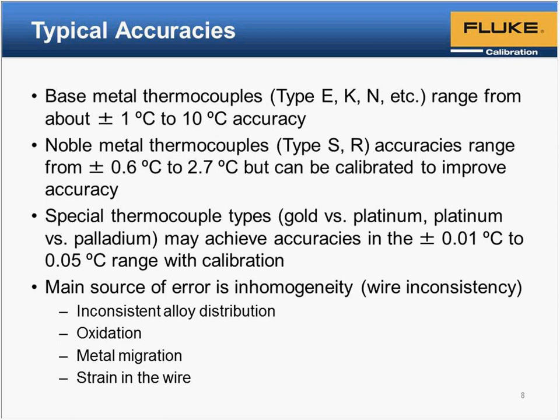So the sources of error, again, are the items that we list here, and some of them change a lot over time depending on how the thermocouple is used. Inconsistent alloy distribution has to do with when the thermocouple is made: how well does the manufacturer mix the alloys together and keep them consistent throughout the length of wire? Oxidation over time, especially at certain temperatures. Then there is metal migration, where a section of wire is heated to a point where the metal vaporizes, and the metal vapor moves and then recollects at a cooler spot in the thermocouple. So you start building up a quantity of a certain metal.